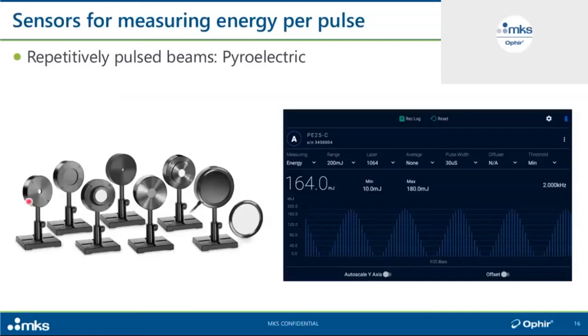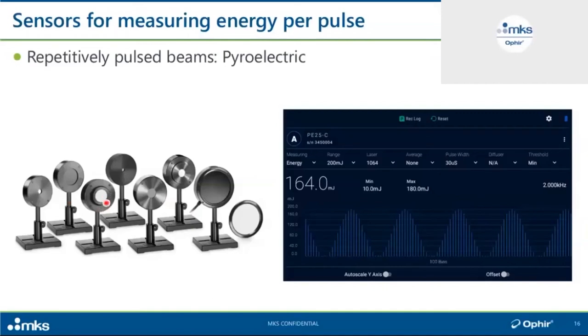For measuring energy per pulse, thermal sensors are unsuitable because their physical time constant is on the order of seconds — they can't respond fast enough to individual pulses. Instead, we use sensors typically based on pyroelectric crystals, which can measure every pulse at rates up to 25 kHz in Ophir's case. Here you see small and large pyroelectric sensors with different absorber types, some with built-in or removable diffusers, and various aperture sizes. A pulse chart example is shown on one of our meters.